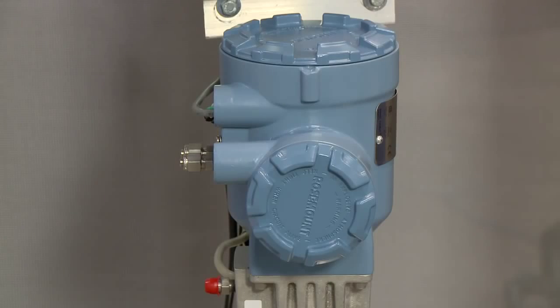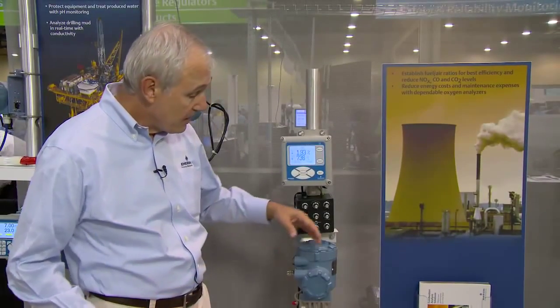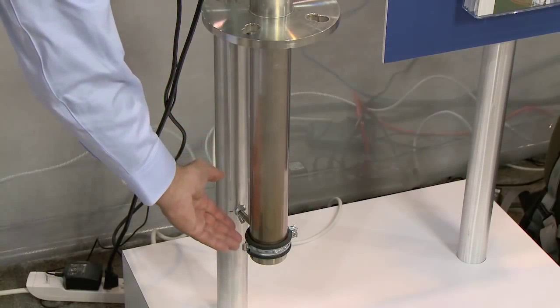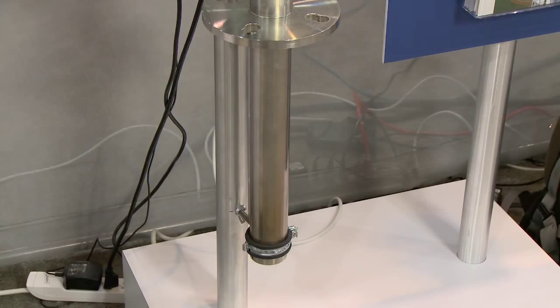require more frequent calibrations. The model 6888 is an InSitu flue gas analyzer for measuring the oxygen remaining in the flue gases from any large combustion process, such as a furnace or a boiler. The product has no moving parts. It has a sensing cell at the bottom that actually measures the oxygen. It is a field rebuildable device. So the sensing cell, the diffuser, the entire guts can be removed and replaced in the field for repair.